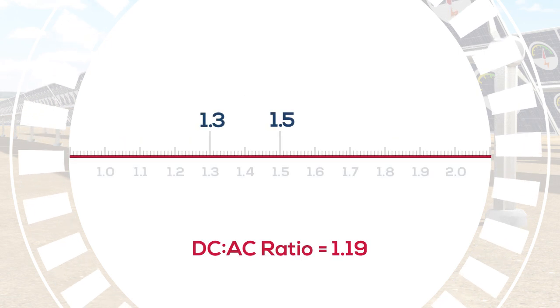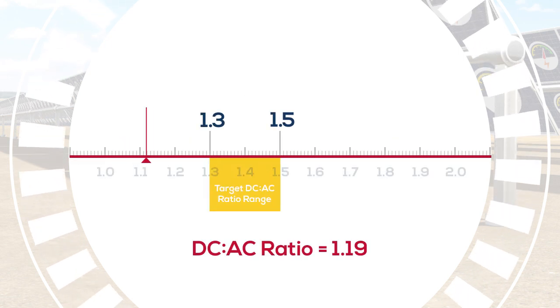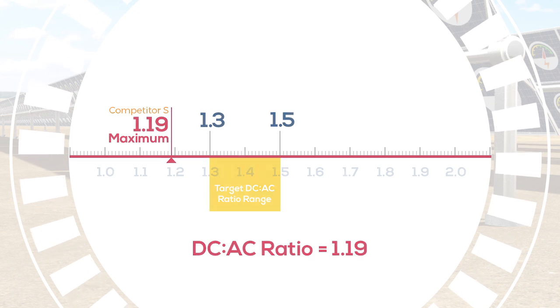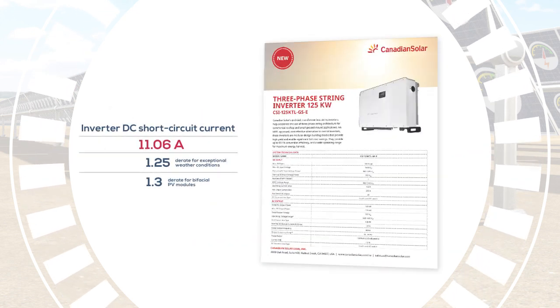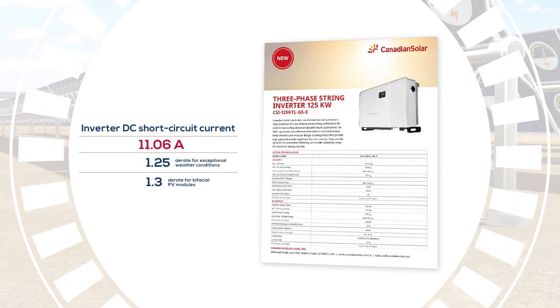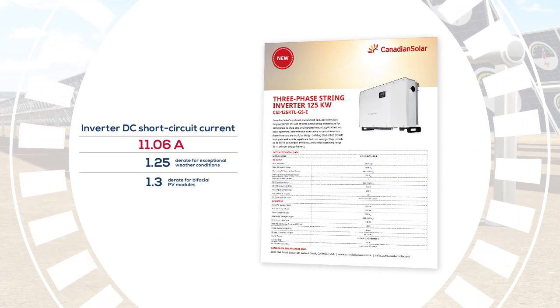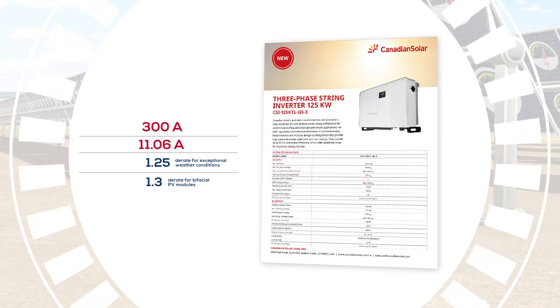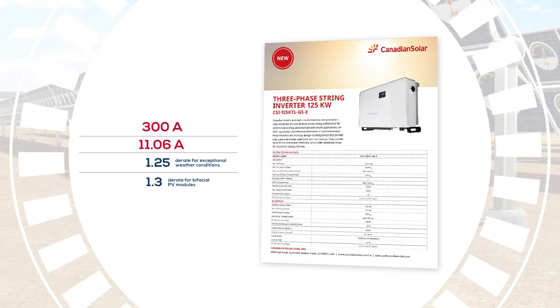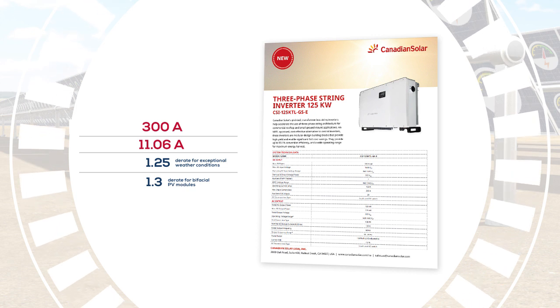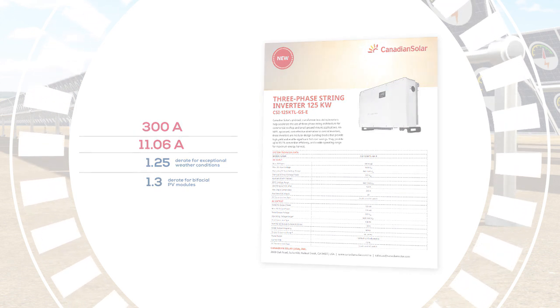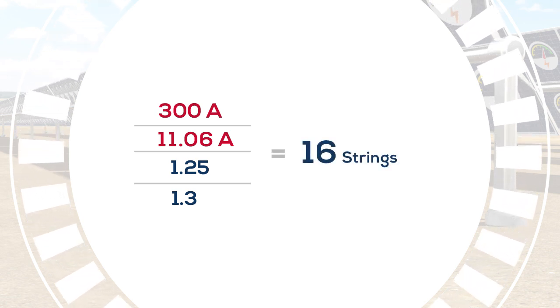That's below the target range of 1.3 to 1.5. Compare that to the same scenario using Canadian Solar's 125-kilowatt inverter, which has a DC short circuit current rating of 300 amps. The number of strings is 300 amps divided by 11.06 amps, divided by 1.25, divided by 1.3, which yields 16 strings maximum.